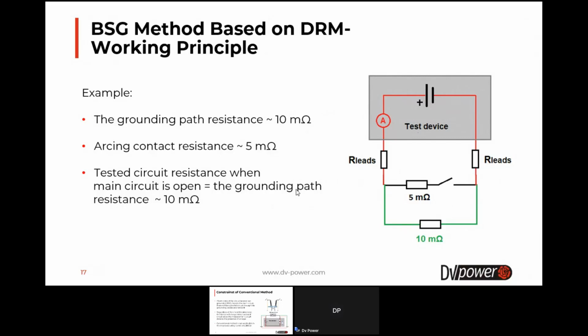Here is one example. So let's say that the grounding path resistance is about 10 milliohms, while the arcing contact resistance is about 5 milliohms. And the equivalent diagram of that circuit is shown in the figure right in this slide. So the resistance of the tested circuit when the main circuit of the circuit breaker is open is equal to the resistance of the grounding path, and it is 10 milliohms in this case.